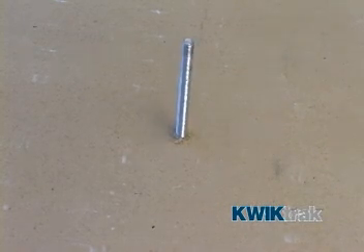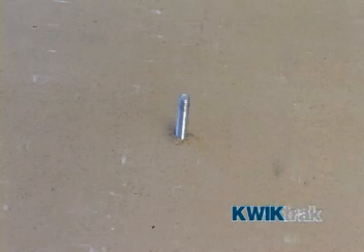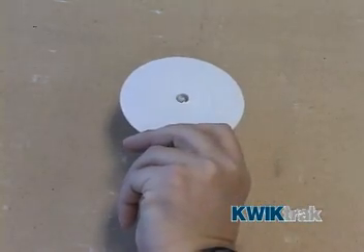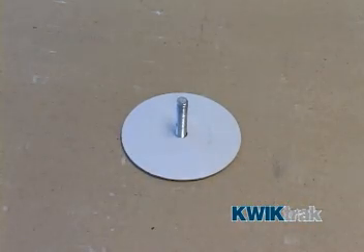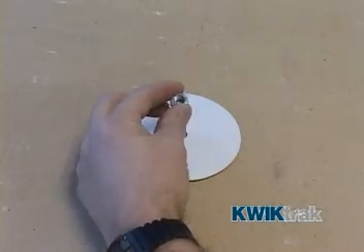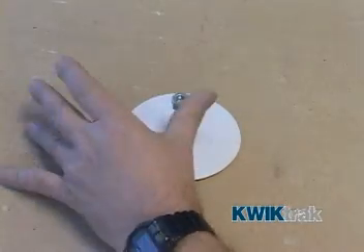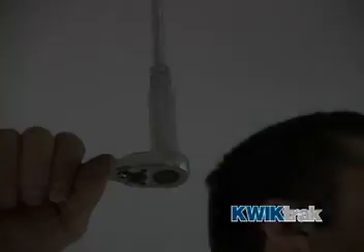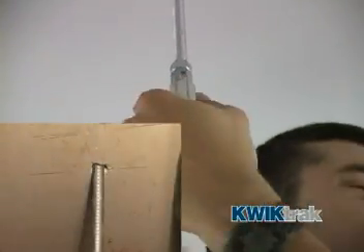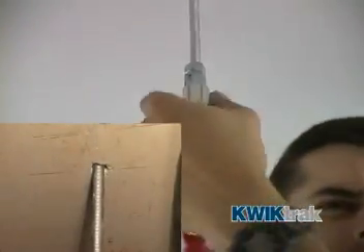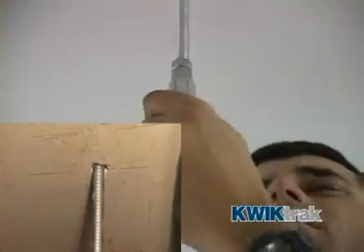If the suspended ceiling is acoustic tile, threaded rod is inserted through the target hole, with the cover plate and nut installed on the back side to add support. The rod is then threaded up and into the installed anchor.